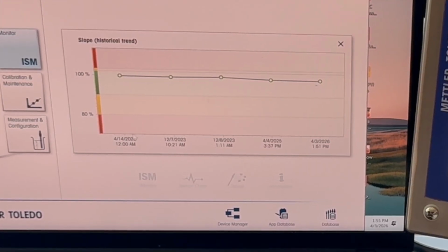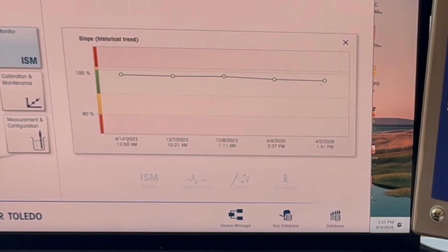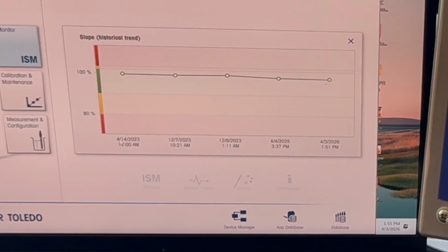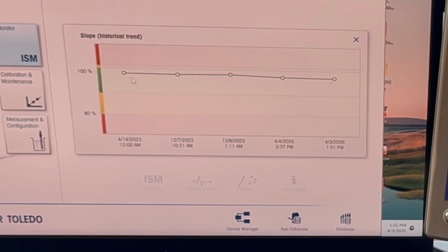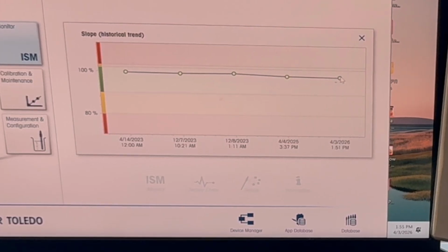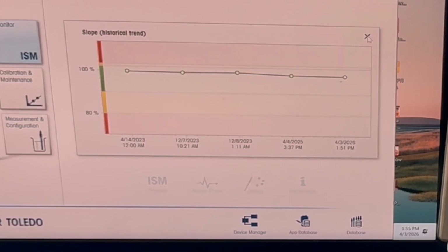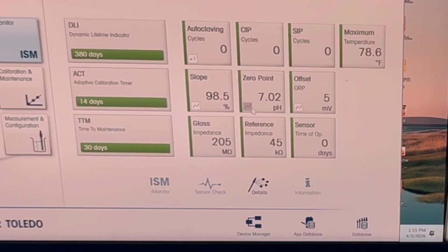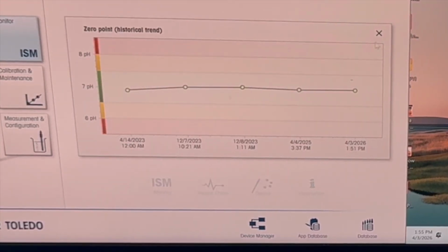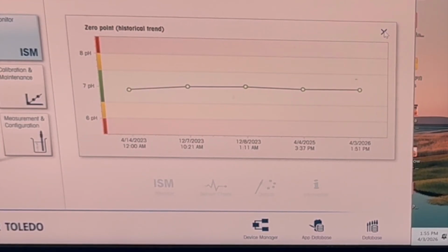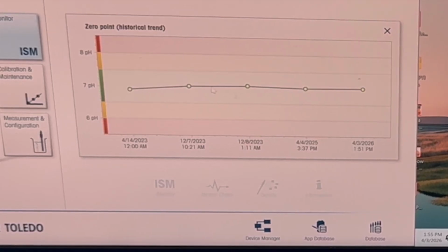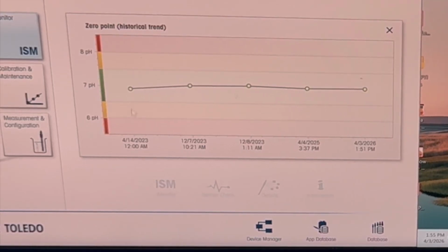You can see the sensors from 2023, actually almost 3 years old, essentially April 14th. So we can actually graphically see how this slope is performing over time. Same with the 0 point. We get this graphical view. So if a sensor was in the process, most likely we would see trending to where it's going into the yellow areas, either above or below that.